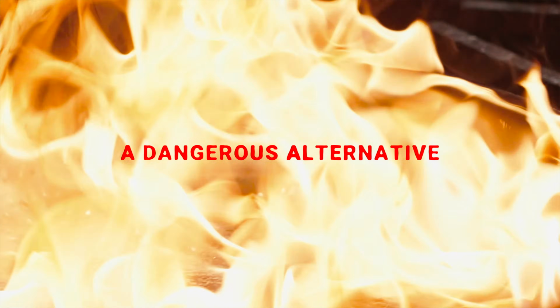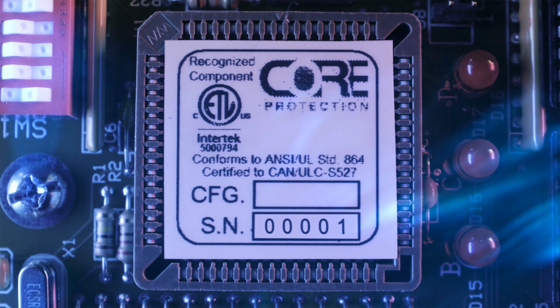Other fire suppression companies, when they develop their systems, they don't develop it with the hood in mind. Actual code and the actual test standards don't even define a hood for testing. You don't have to have a hood while you're testing fire suppression systems. When I first found out about that, I was blown away. They just string up nozzles on unistrut frames, and they put appliances underneath of it, and they just hang nozzles in midair, no hood above it, just in midair, and just determine how effective it is at suppressing appliances. So they have no idea how airflow interacts with fire suppression, no idea how the hood impacts suppressing fires, in panels, controls. That's all up to the hood company to figure out. So if you have the hood company over here and the fire suppression company over here not communicating with one another, how's the system ever supposed to work correctly? We've eliminated that. We've combined them together for a factory solution.